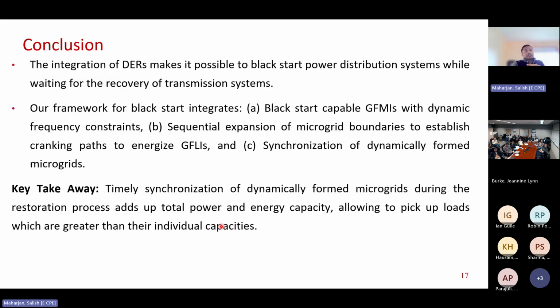Okay, so these are the main results, and the conclusion of this research says that integration of DERs makes it possible to blackstart the distribution system while waiting for the recovery of the transmission system. So our framework integrated blackstart capable grid forming inverters with dynamic frequency constraint and helped the microgrid to sequentially expand their boundaries to bring other grid following inverters online. And it also modeled synchronization of dynamically formed microgrids.